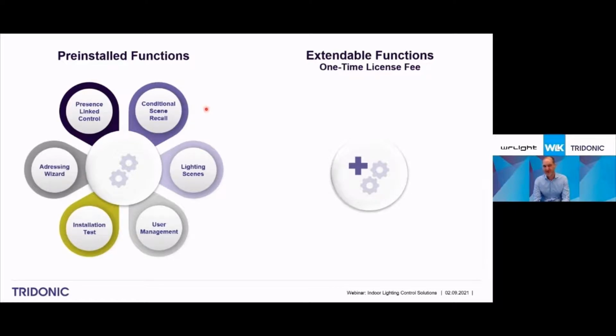One of the coolest things we have is the addressing wizard, where we have routines and logic built into the web interface to make commissioning and setup of a DALI system really easy, without bringing back all those DALI short address group complications in a cumbersome way, but in a way that's intuitive for users to set up a system with rooms, groups, devices, sensors. That's all then handled in the background by the wizard.